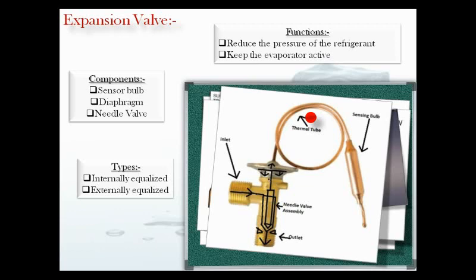An externally equalized thermostatic expansion valve compensates for any pressure drop through the evaporator. The high pressure liquid refrigerant entering the expansion valve is quite warm, which may be verified by feeling the liquid line at its connection to the expansion valve. The liquid refrigerant leaving the expansion valve is quite cold. The orifice within the valve does not remove heat, but only reduces the pressure. Heat molecules contained in the liquid refrigerant are allowed to spread as the refrigerant moves out of the orifice, so the liquid refrigerant is at its coldest as it leaves the expansion valve and enters the evaporator.